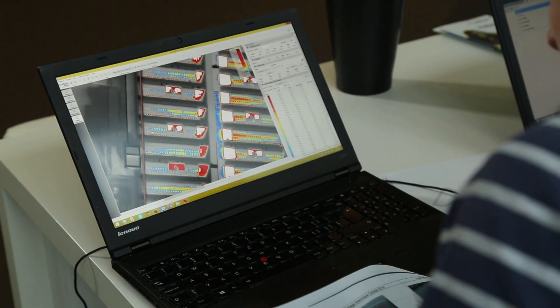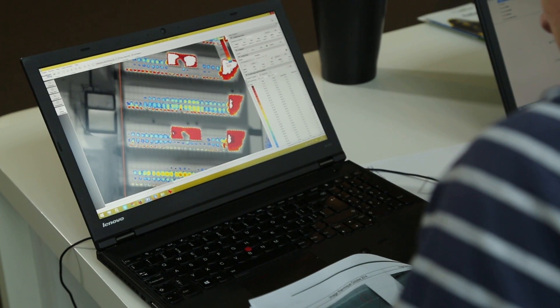We also managed to identify the probable causes of the hot spots. Certain are clearly due to shading, which we can't do much about, but others are mostly due to malfunction or broken panels, which will enable us to guide our maintenance team in order to intervene and replace panels if necessary.